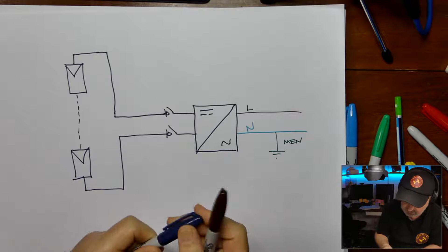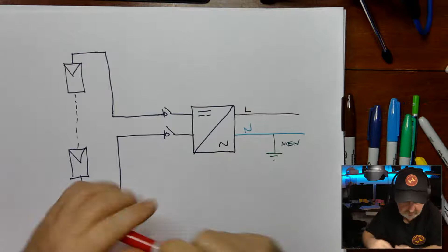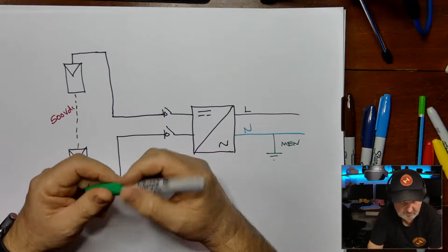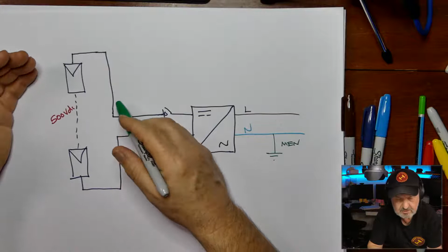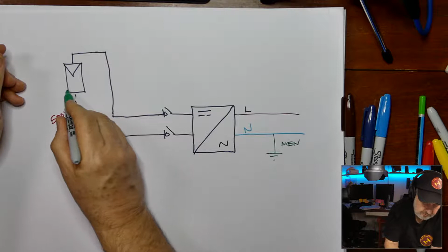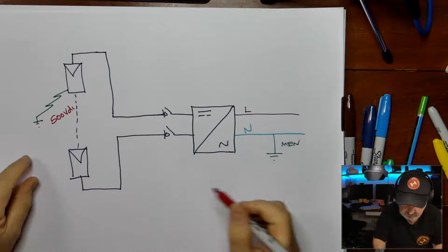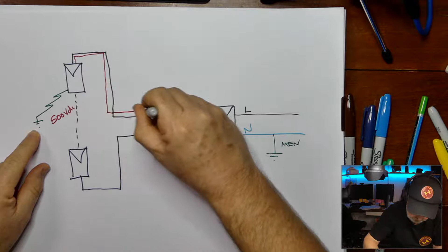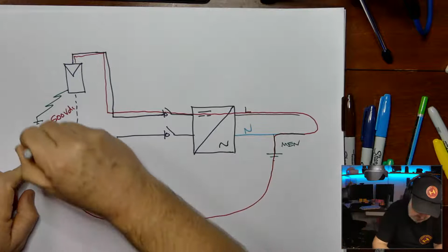For those who are not from Australia or New Zealand, we have a strange earthing system called TNCS, which bonds the neutral to earth at the customer's premises at the main switchboard. Now, if we've got an array operating at, say, around 500 volts DC, and someone installing the system or some other creature that's come along has caused a fault, something like a pinched cable or a chewed cable, and it touches onto the earthed array, it will cause an earth fault at some point. I'm drawing that as a fault to earth. Now we have an alternative way of returning that current. The current can flow through here, and this is the scary bit, goes through the transformer in the street and all the way back to here. That's the path of the fault current.